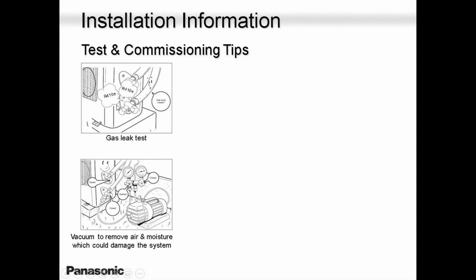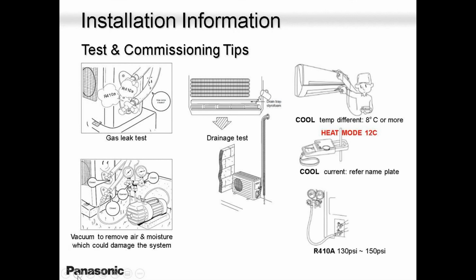Pressurize your system. Always use nitrogen. Now don't over pressurize it. For a small system, 200-300 psi is more than enough. Why am I saying 200-300? I know pressure is pressure. 400 is pressure, 300 is pressure. But why am I saying lower pressure on a lower system? Because of these valves here. You see the service valve? The moment you give it too much pressure, it may push the rubber seal inside, and some of the R410 will escape. And you don't want that to escape, because I will show you in the next few slides what's going to happen.